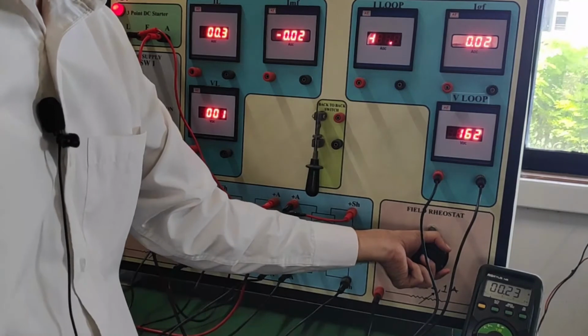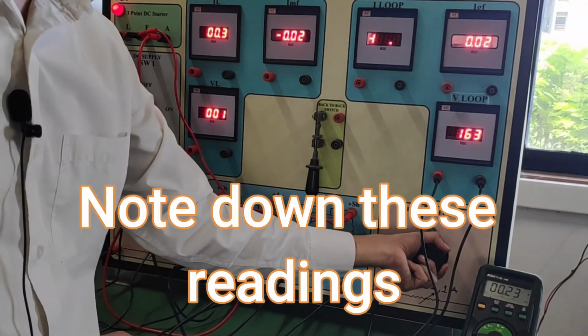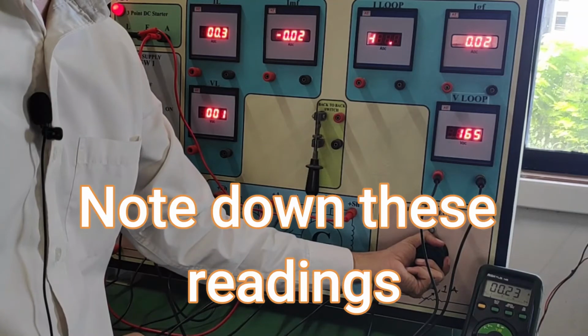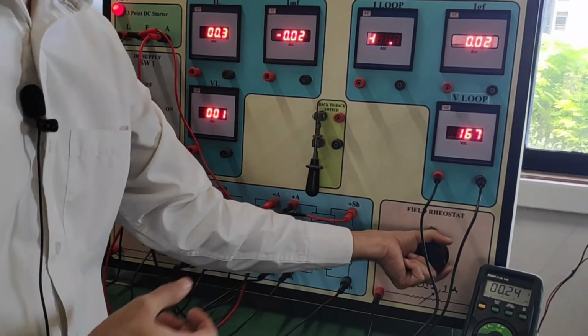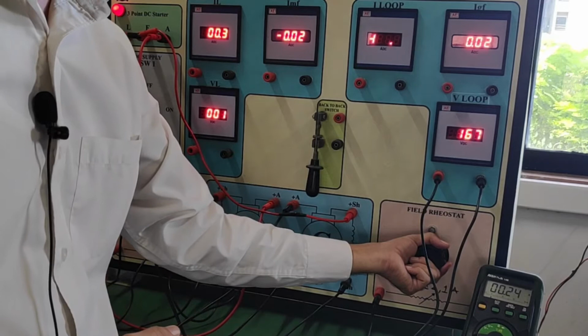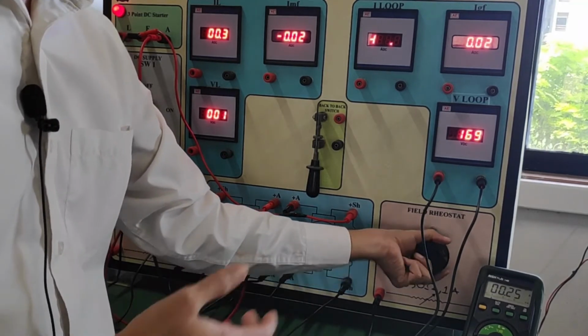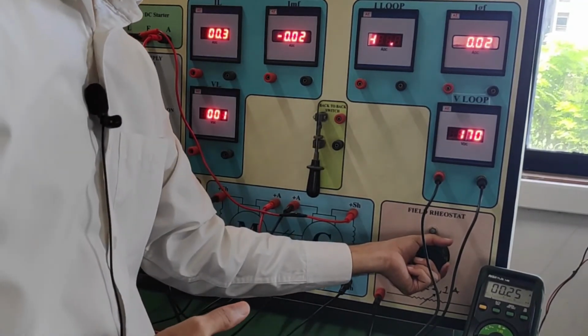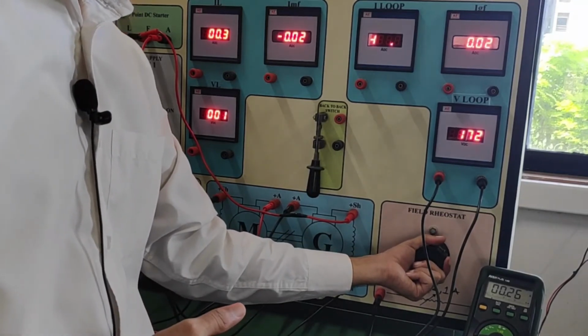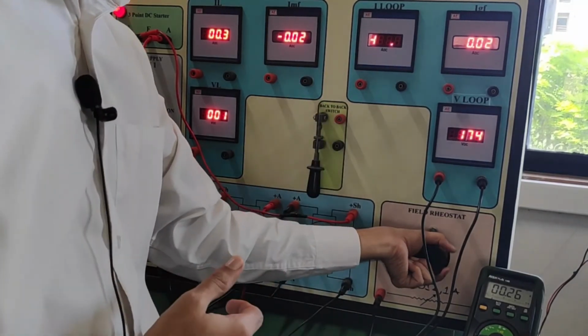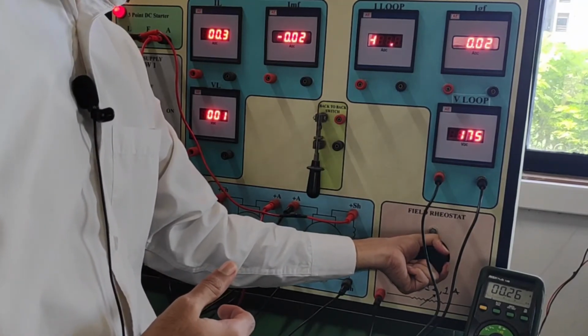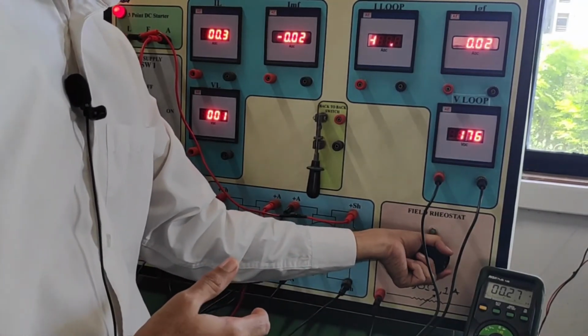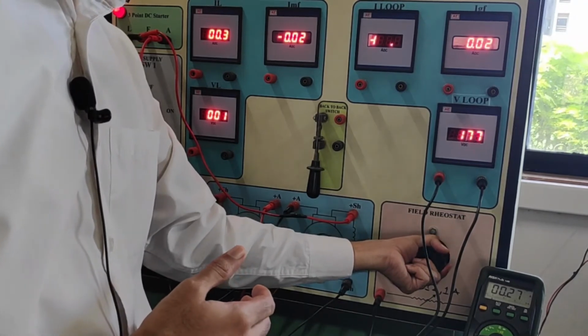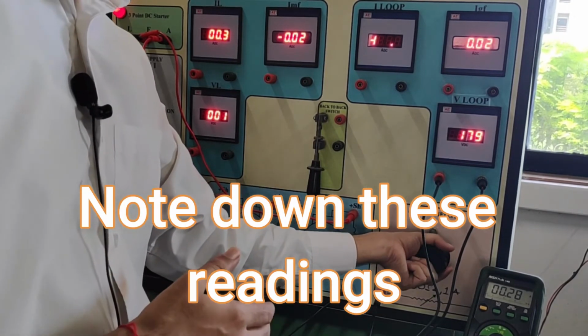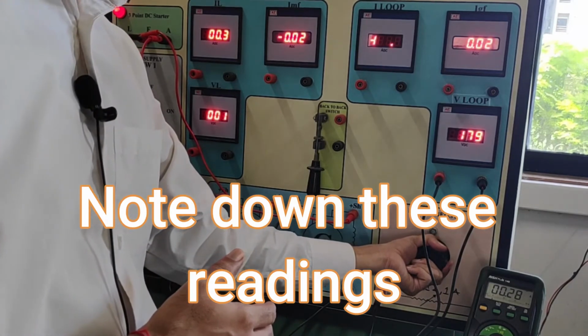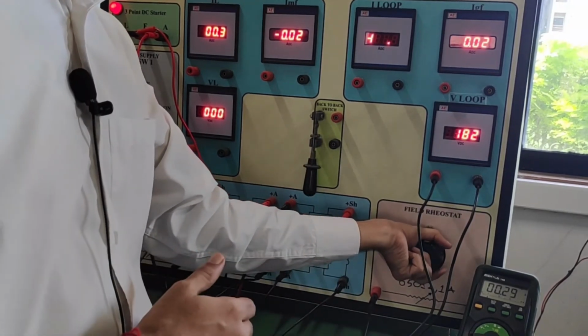Field excitation is 0.23 and voltage is 162. 0.24 and the voltage is 167. 0.25 and the voltage is 170. 0.26 and the voltage is 173. 0.27 and the voltage is 176. 0.28 and the voltage is 179. 0.29 and the voltage is 182.